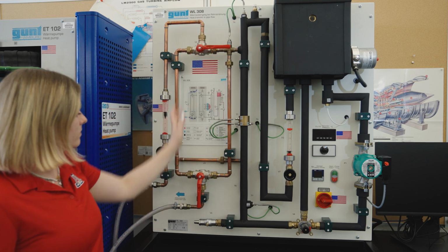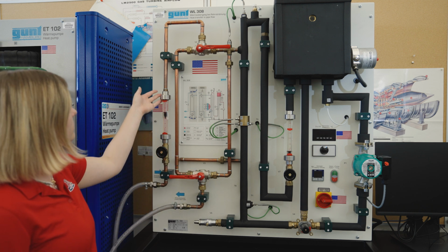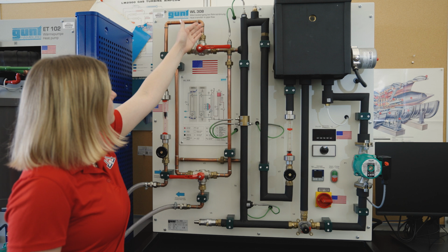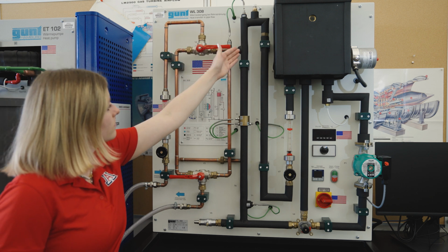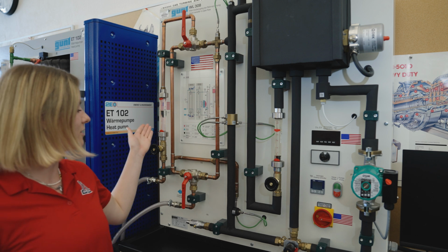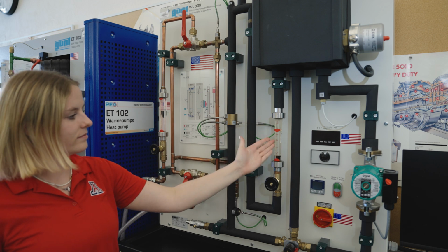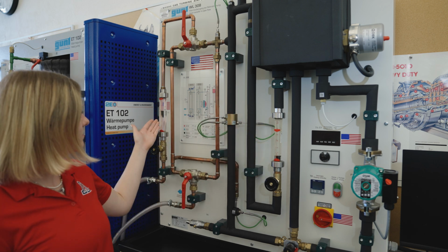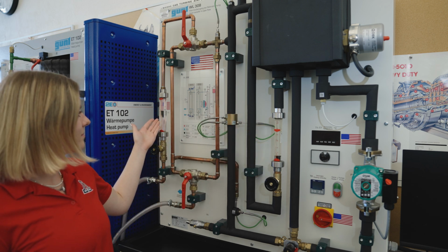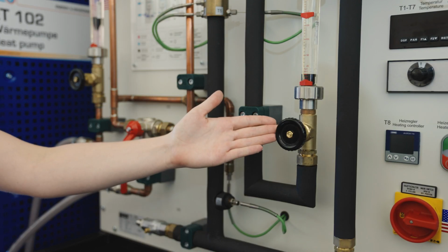When the valve handles are in horizontal and anti-parallel positions, the heat exchanger operates in the counterflow configuration. A rotameter for the cold water inlet ensures that water is flowing through the device at the appropriate rate, and a rotameter for the hot water inlet ensures that hot water is flowing from the heater to the heat exchanger at the proper rate. These flow rates can be adjusted using the black valves located by either rotameter.